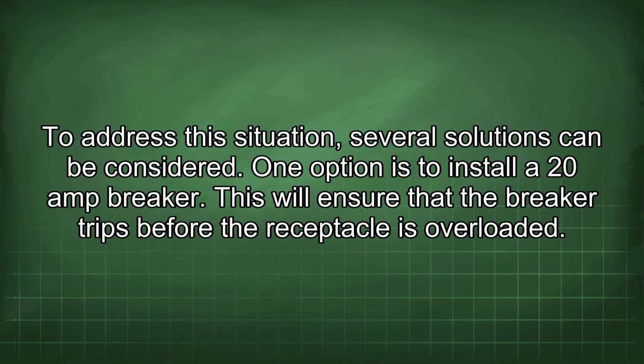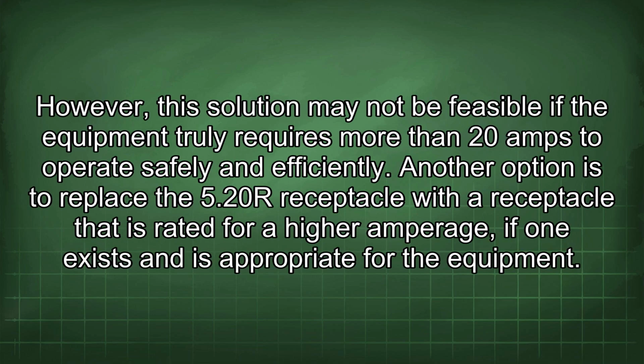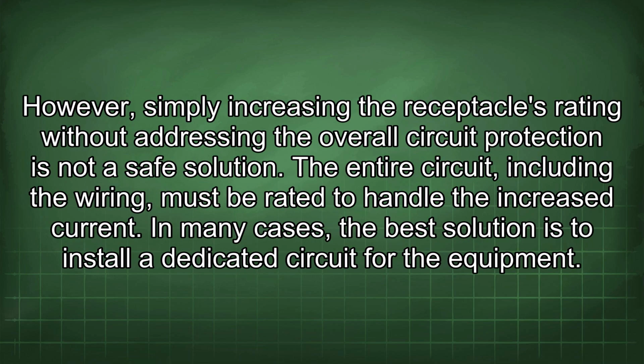One option is to install a 20 amp breaker. This will ensure that the breaker trips before the receptacle is overloaded. However, this solution may not be feasible if the equipment truly requires more than 20 amps to operate safely and efficiently. Another option is to replace the 5.20R receptacle with a receptacle that is rated for a higher amperage if one exists and is appropriate for the equipment. However, simply increasing the receptacle's rating without addressing the overall circuit protection is not a safe solution. The entire circuit, including the wiring, must be rated to handle the increased current.